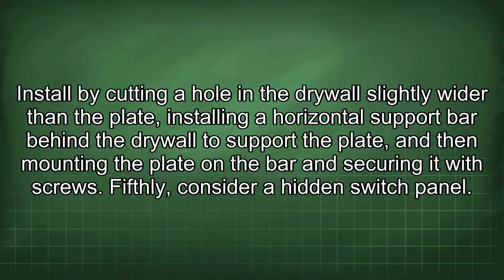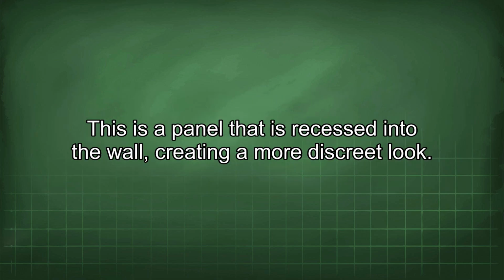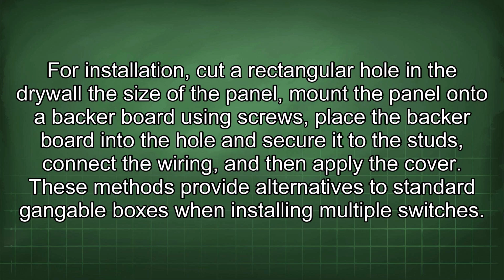Fifthly, consider a hidden switch panel. This is a panel that is recessed into the wall, creating a more discreet look. For installation, cut a rectangular hole in the drywall the size of the panel, mount the panel onto a backer board using screws, place the backer board into the hole and secure it to the studs, connect the wiring, and then apply the cover. These methods provide alternatives to standard gangable boxes when installing multiple switches.